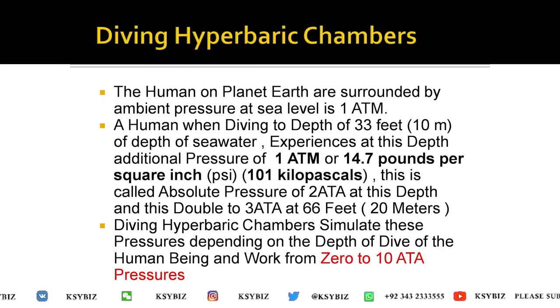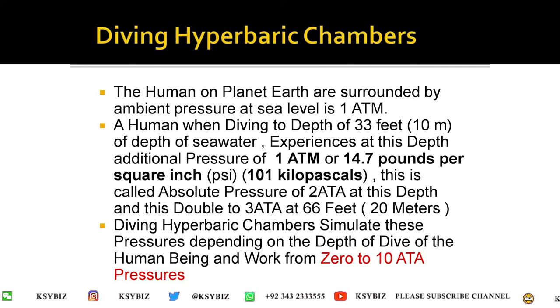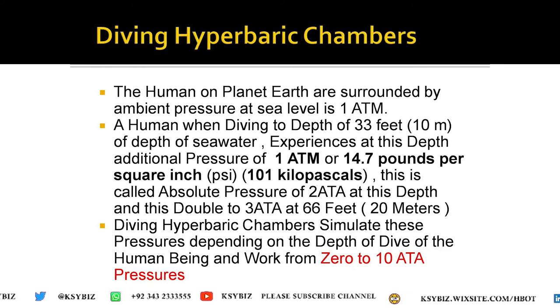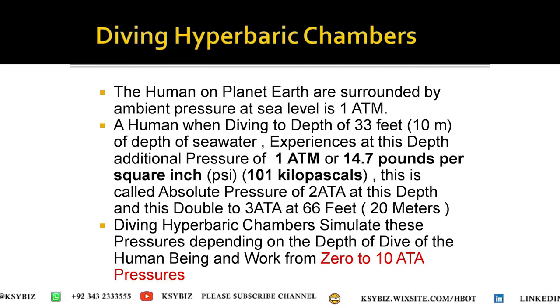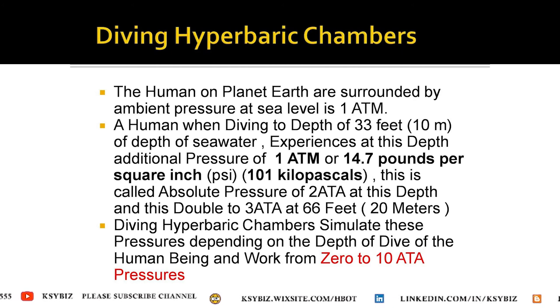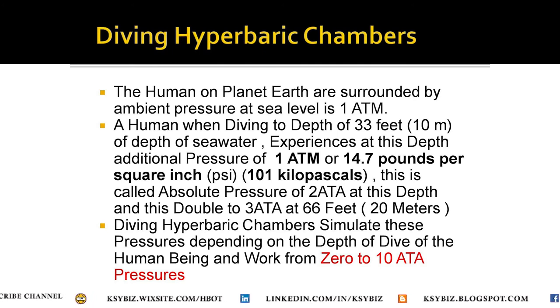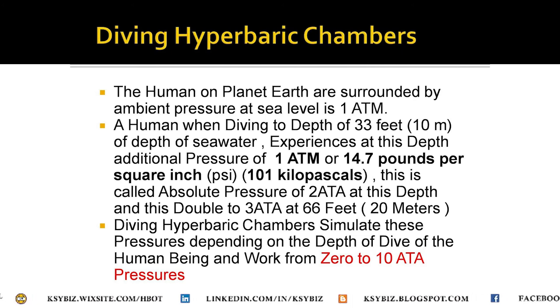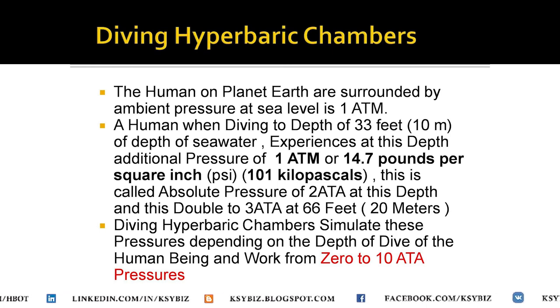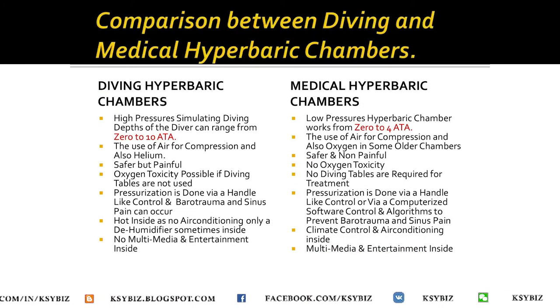In the diving hyperbaric chamber, humans are surrounded by ambient pressure at sea level equal to one atmosphere. When diving to a depth of 10 meters, a diver experiences one additional atmosphere — 14.7 pounds per square inch or 100 kilopascal — giving an absolute pressure of 2 ATA. At 33 feet (10 meters) the absolute pressure is 2 ATA, at 66 feet (20 meters) it is 3 ATA. Diving chambers simulate these pressures according to dive depth, with a working pressure range of zero to 10 ATA.